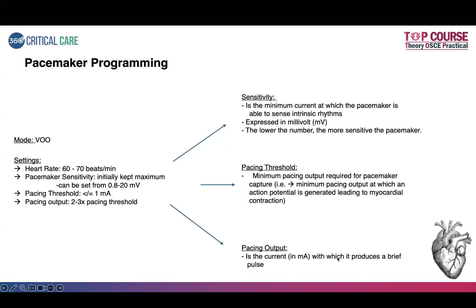So, like I said, the heart rate should be set between 60 to 70. The pacemaker sensitivity should be kept on the higher side initially and then reduced gradually. The lowest should be 0.8. The lower the number, the more sensitive the pacemaker. Then, the pacing threshold. It is the minimum pacing output required for the pacemaker capture. So what is this capture? That is the minimum pacing output at which an action potential is generated, leading to a myocardial contraction. And the pacing output should be 2 to 3 times the pacing threshold. The pacing output is nothing but the current with which it produces a brief pulse.